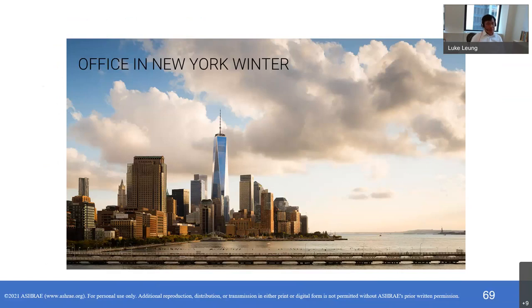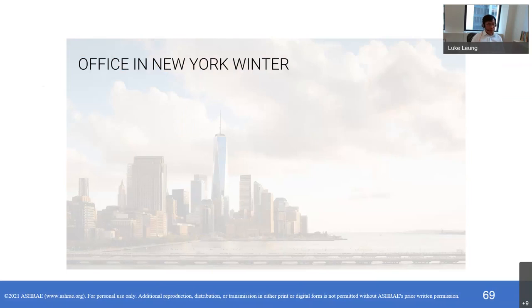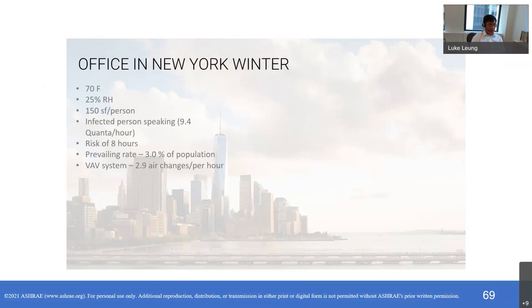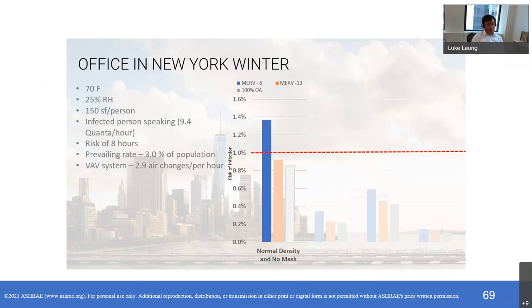So finally, we're going to run through what type of risk we are looking at if we do the minimal outside air with a high MERV filter. This is an office building in New York State. Next slide. So the first case we look at is, next slide. Those are the assumptions, you can go through that later. So next slide. The first case here, the blue, is the space with no masks and 100% occupancy rate, which is going to be above 1%. Next slide. But, next slide. Next slide.